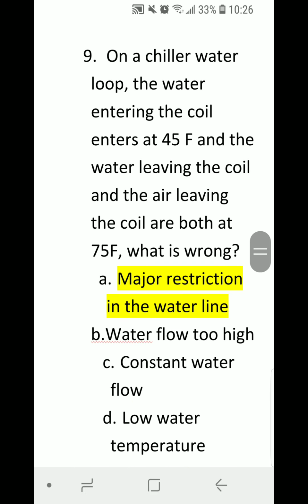Number 9. On a chiller water loop, the water entering the coil enters at 45 Fahrenheit, and the water leaving the coil and the air leaving the coil are both at 75 Fahrenheit. What is wrong? A. Major restriction in the water line. B. Water flow too high. C. Constant water flow. Or D. Low water temperature. Correct answer is A. Major restriction in the water line.